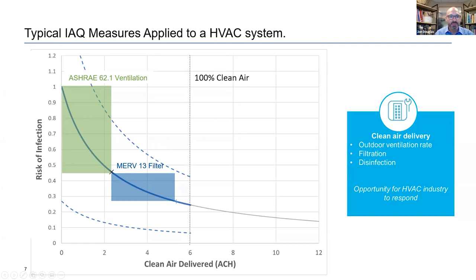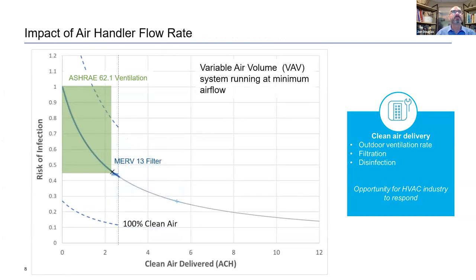So in this next slide, I want to illustrate what happens when you have a variable air volume system and it runs at its lowest airflow. Variable air volume systems vary the airflow rate based on load. It's designed to save energy. In this case, the VAV system is at a low load and it's reduced its airflow rate. We still get the benefit of the ASHRAE ventilation because the outdoor air dampers adjust to maintain a constant ventilation rate, because the occupancy is constant. But because the airflow rate is lower, we don't get that much benefit from the MERV 13 filter. So again, the benefit is a function of load.